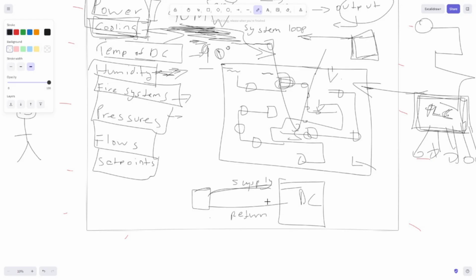Okay, my mic died. I was rudely interrupted, but what we were saying is an air conditioning unit is a chilled water system, right? It has a supply sending cold water into the data center and then hot water outside of the data center so that it gets cooled, right? But with the air conditioning unit, you have to have a differential, a difference in the pressures of the flow. Let's say this is like 90 flow, and this is like 70 flow. The difference is 20. That tells you that we actually have water flowing. That's pressure differential right there, right?